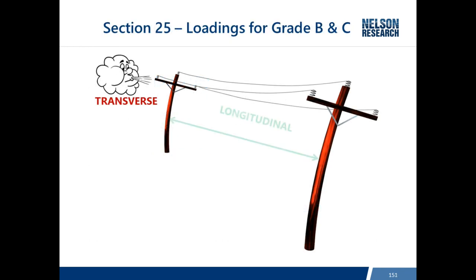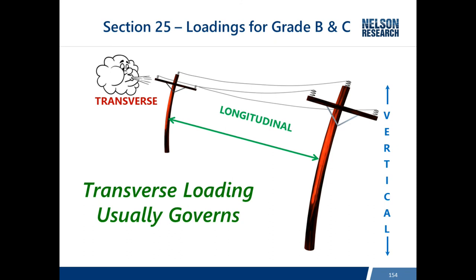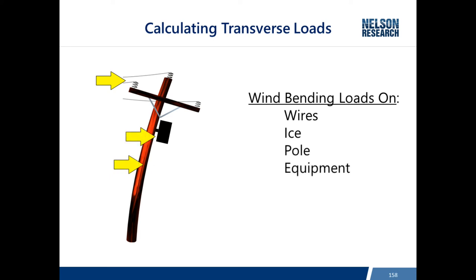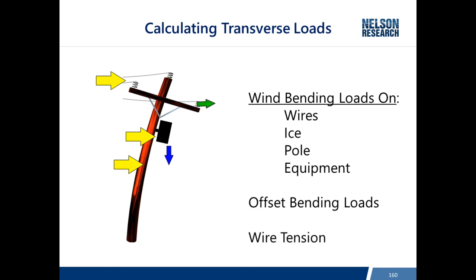Besides transverse loading on a pole, there is longitudinal loading in the direction of the wires and vertical loading from equipment and other weight imposed on the poles. Generally, transverse loading governs — if a pole is strong enough to support transverse wind loads, it is also strong enough to support vertical and longitudinal loads. Transverse loads come from wind on wires, ice, wind on the pole and equipment, equipment offset weight, and wire tension at angles.